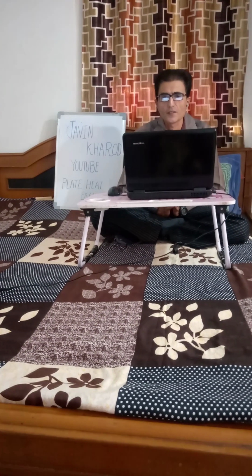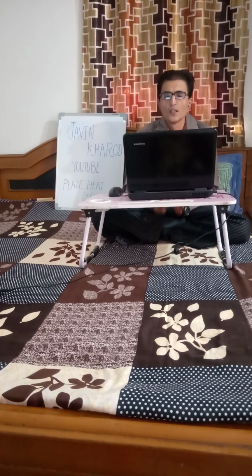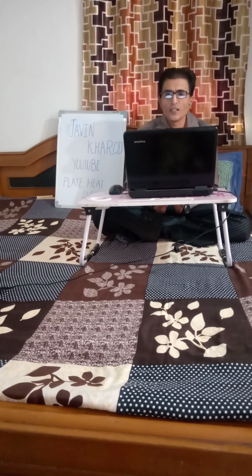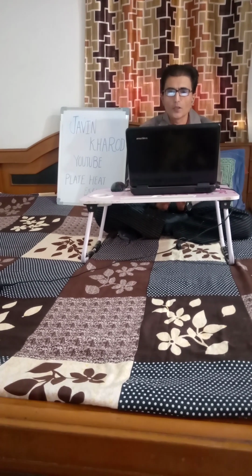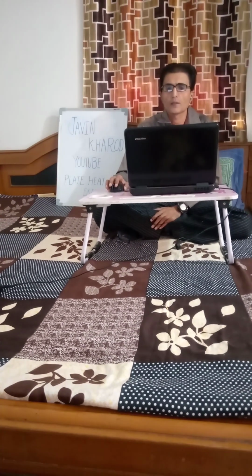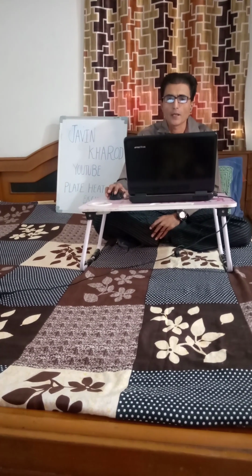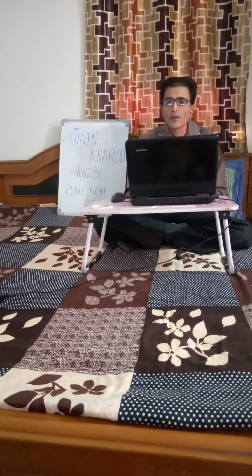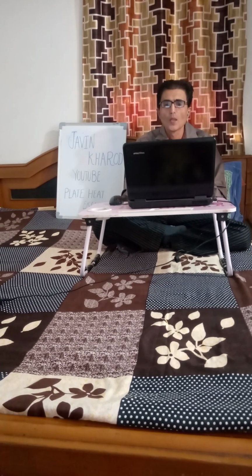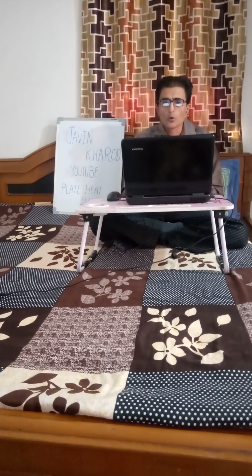Now, evaluating plate heat exchangers. All plate heat exchangers look similar on the outside. The differences lie on the inside: the detail of the plate design and the sealing technology used. Hence, evaluating a plate heat exchanger is very important. Not only explore in detail the product being supplied, but also analyze the level of research and development carried out, manufacturing, post-commissioning services and spare part availability. An important aspect to take into account when evaluating heat exchangers is the form of corrugation within the heat exchanger. There are two types: intermating and chevron corrugation.